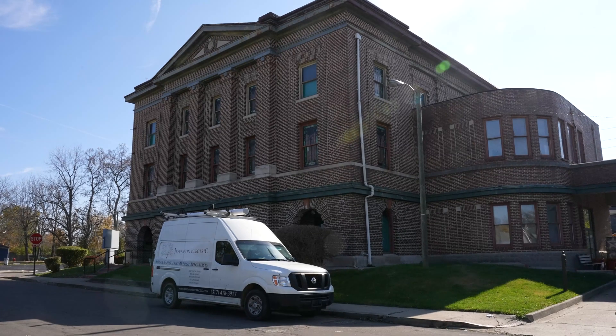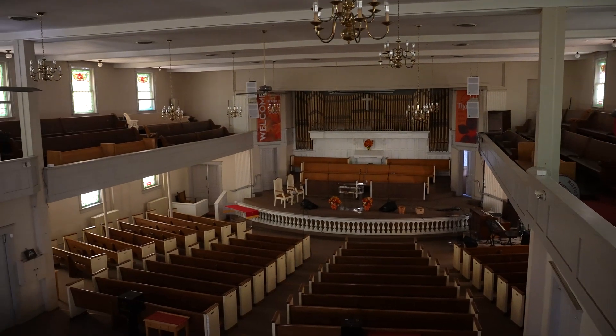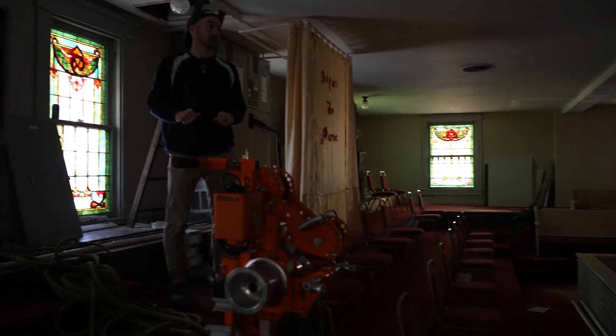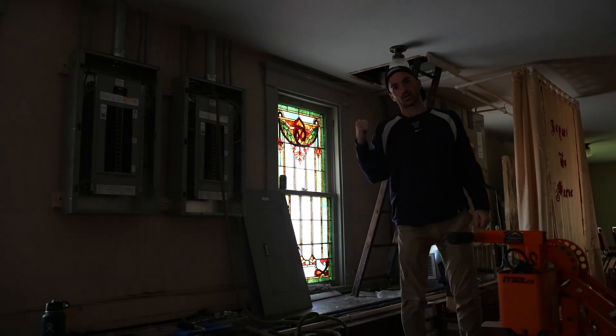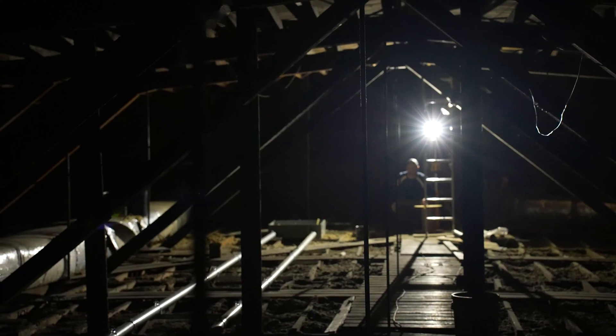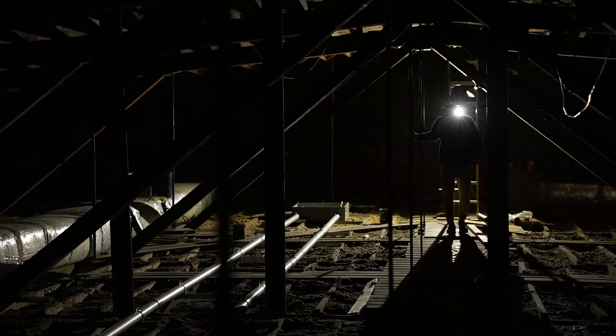This is the front of the building — all the service equipment's in the back though. The sanctuary space is beautiful, and that's because they've hidden all of the electricals and HVAC up in the attic. We've got to go up one more level to see where these main panels are being fed. At the top of the ladder, look at the scale — there's a giant pull box and then 100 feet of 2.5-inch EMT spanning the entire attic space above the sanctuary.